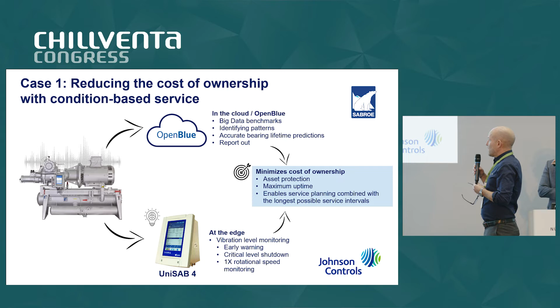And to maximize uptime, but also to enable our customers to efficiently plan their service to fit into their production plans. On the controller level, in this case, we can monitor vibration levels on the compressor and motor bearings and give an actual picture of the condition of the bearings. Then, at the local controller level, it's possible to protect the equipment against wear, and against complete wreckage of the machine.